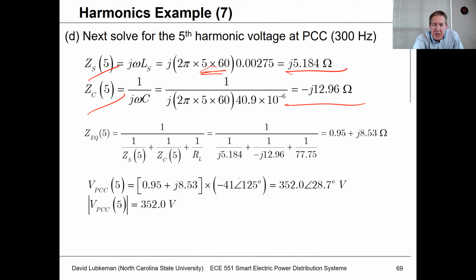And what I get in this case, if I inject the current associated with the load, and I have to put a minus here because I need this injected, is going to give me a magnitude of 352 volts. And so I do have a pretty significant voltage at that bus at the 5th harmonic.